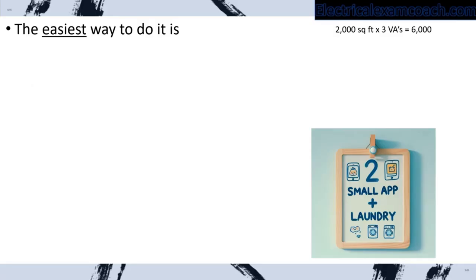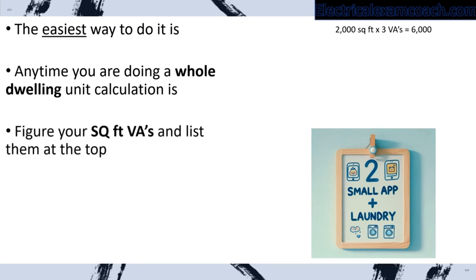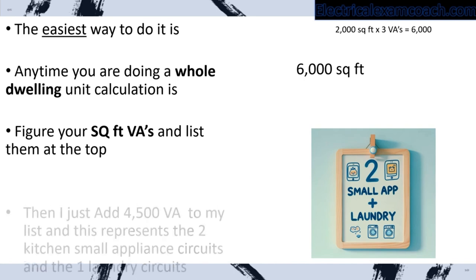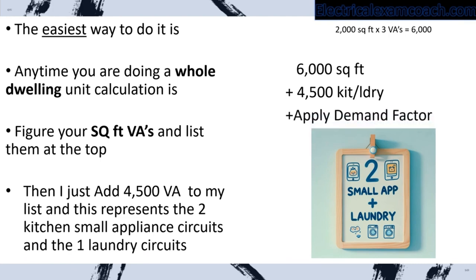The easiest way to do it is: any time you're doing a whole-dwelling-unit load calculation, take your square footage and multiply it by 3 VAs per square foot. Let's imagine a 2,000 square foot house: 2,000 multiplied by 3 VAs equals 6,000 VAs. Then you just tack on the 4,500 for the 2 small appliance and 1 laundry circuit — and only if you're doing a whole-home load calc.